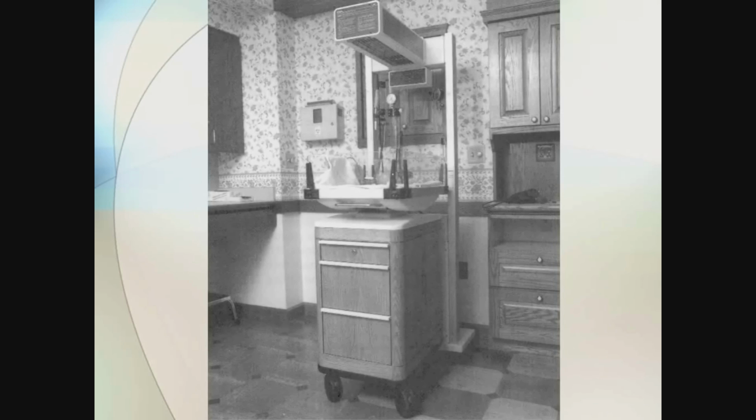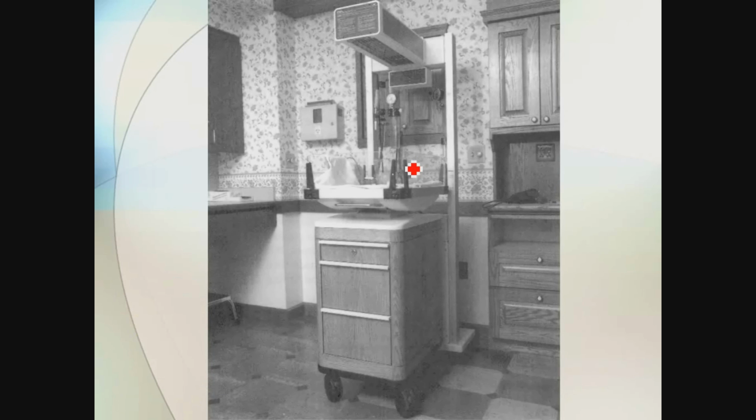And this is what the radiant warmer looks like, and I don't know if you can see this really well or not. But there are little walls here that are up, and that prevents that convective loss of air moving across. And this is where I was talking about taking a piece of cellophane and just placing it right over the top to maintain the heat on the inside. And the heat source obviously is right up here, going down.